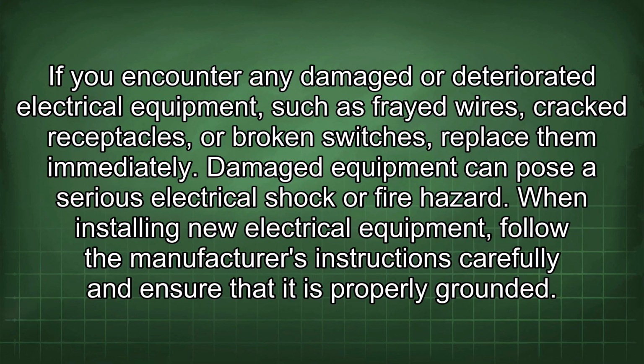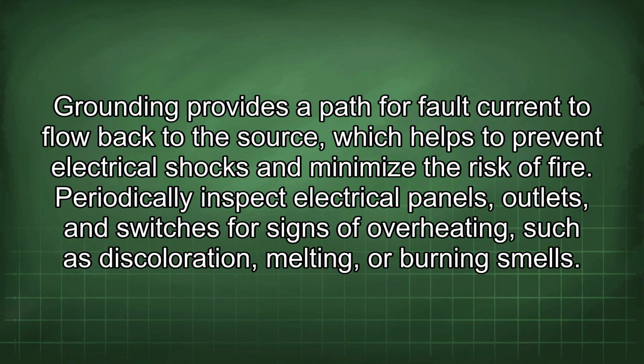When installing new electrical equipment, follow the manufacturer's instructions carefully and ensure that it is properly grounded. Grounding provides a path for fault current to flow back to the source, which helps to prevent electrical shocks and minimize the risk of fire.